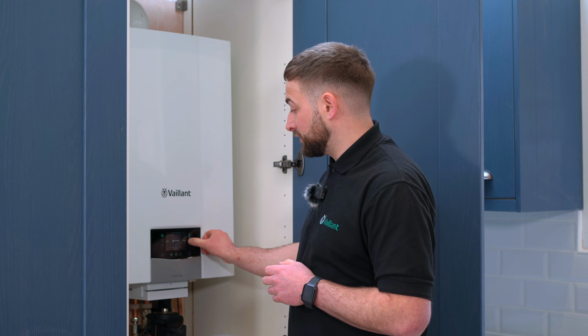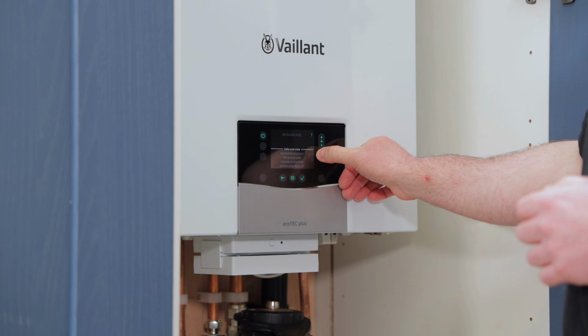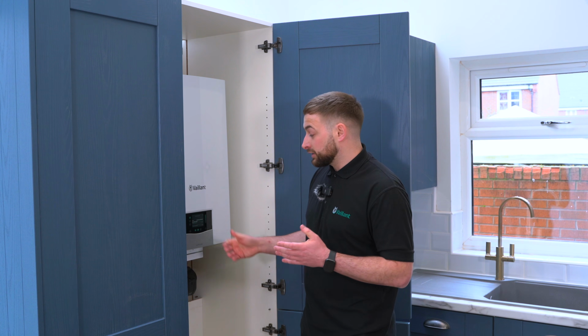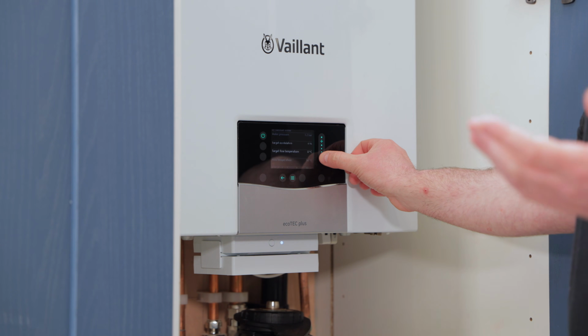We access the diagnostic codes through the installer level within the settings. Once we input the access code, we can now look at the data overview as an example, which gives us some key data points to show us what the boiler is doing at this moment in time. That includes things like the status, so whether the boiler is actually on or off. It shows us the target modulation percentage, it shows us the water pressure, and a variety of different target and actual temperatures throughout the appliance itself.